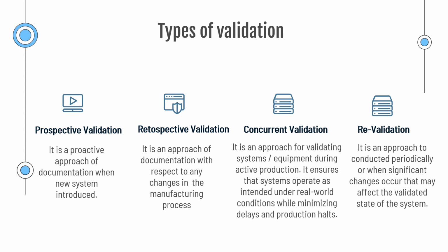Types of validation. Prospective validation. It is a proactive approach of documentation when a new system is introduced. Retrospective validation. It is an approach of documentation with respect to any changes in the manufacturing process. Concurrent validation. It is an approach for validating systems and equipment during active production. It ensures that systems operate as intended under real-world conditions while minimizing delays and production halts. Revalidation. It is an approach to conduct it periodically or when significant changes occur that may affect the validated state of the system.